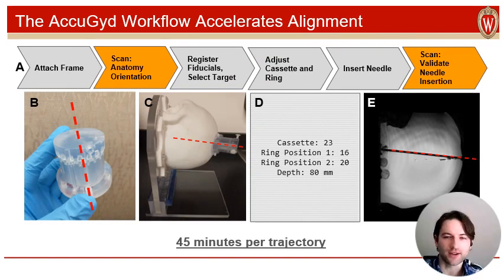Our device, the AccuGyd, circumvents this iterative phase by allowing the trajectory alignment to be achieved in 45 minutes using only a single scan. Users attach the guide, take one scan, and then using a target picked on that scan, companion software will tell users specific quantized adjustments to make to the device's configuration to aim the channel appropriately. Users may then immediately move to inserting their devices through its channel. This workflow has been validated in both a series of phantom trials and tests performed on human cadavers.